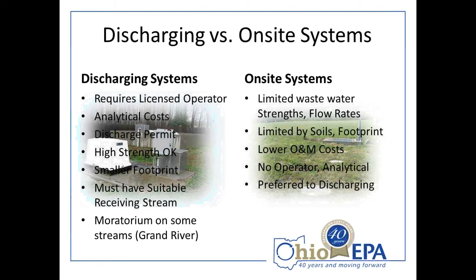There are advantages to both discharging systems and on-site systems. A discharging system requires a licensed operator under Ohio EPA's operation rules 3745-7, has analytical costs, requires a discharge permit, and can handle high-strength waste. The system can have a smaller footprint than an on-site system, but you must have a suitable receiving stream. For example, in my district there is a moratorium against new discharges for the Grand River Watershed, so be aware of any restrictions on your watershed.